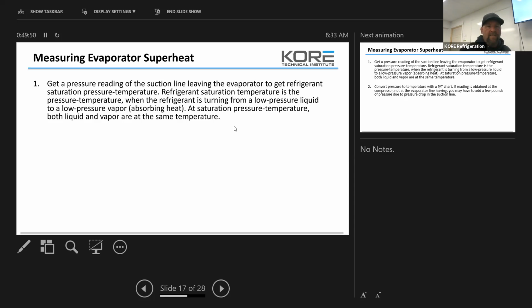Okay. So take the gas pressure reading of the suction line leaving the evaporator to get refrigerant saturation pressure temperature. Refrigerant saturation temperature is the pressure temperature when the refrigerant is turning from a low pressure liquid to a low pressure vapor, absorbing heat. So at saturation pressure temperature, both liquid and vapor are at the same temperature. Okay. So when you guys are doing your superheat calculations, you always need to come off the suction line at the closest port coming right out of the evaporator. At supermarkets, there's always a suction port right there at the evaporator case. If you're dealing with a small unit, you're probably going to have to gauge up at the compressor, and then you're going to have to add a couple PSI for your heat pickup, and your manufacturers can tell you what that is.